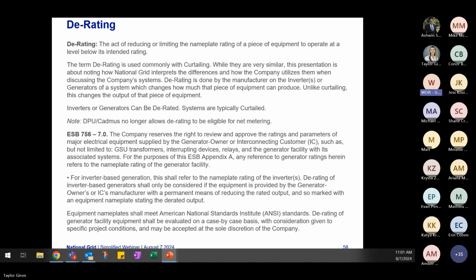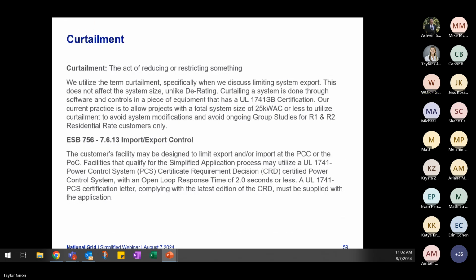Our current practice is to allow projects with a total system size of 25 kWAC or less to utilize curtailment to avoid system modifications and avoid ongoing group studies for R1 and R2 residential rate customers only. Below is our ESB 756 section on import and export control that covers power control systems. Next slide, please. And the next one.